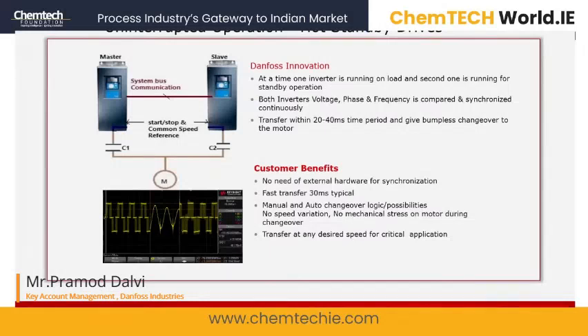Alternately, I think this is not done in this case story, but this is another feature in Danfoss premium drives, that we can also do the hot standby configuration. In this case, one inverter is running on load and the second one is on standby operation. Both are working, and both waveforms are checked for healthiness. In case one drive fails, then automatically within 20 to 40 milliseconds the other takes over with a bumpless changeover. For very critical applications, we have seen even in process fans, ID fans, refinery and chemical industry opting for standby drives. We are working with a lot of end users on requirements of this. So this can also be one solution which some of the contractors, consultants and end users are working on in this segment.